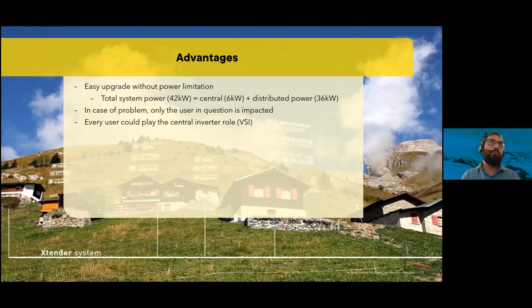In case of problem, only the user in question is impacted. One interesting thing is that every user could play the central inverter role, it's only configuration. So if the central inverter has a problem, another can take over and play the central inverter role. Very flexible to integrate new users, whether producer, consumer, or prosumer. The energy distribution is done with very reduced cable size, so for the distribution line, it's very interesting because we are not bringing power to all the users.